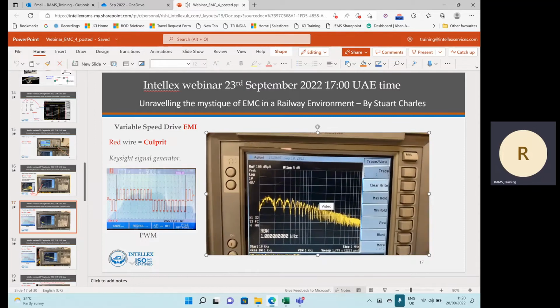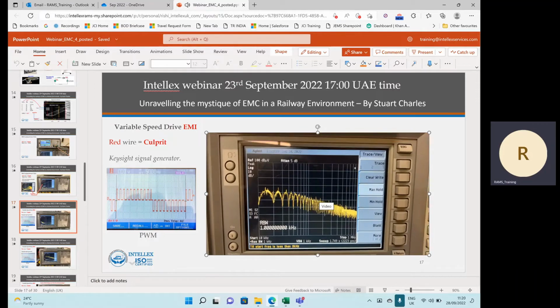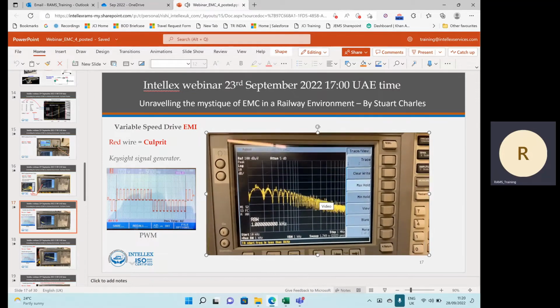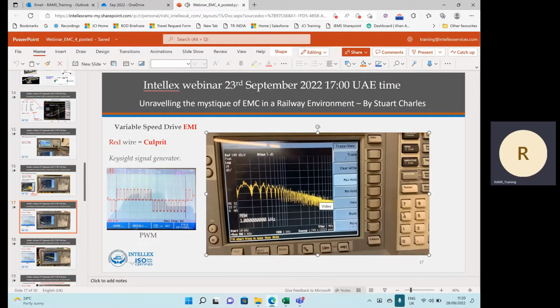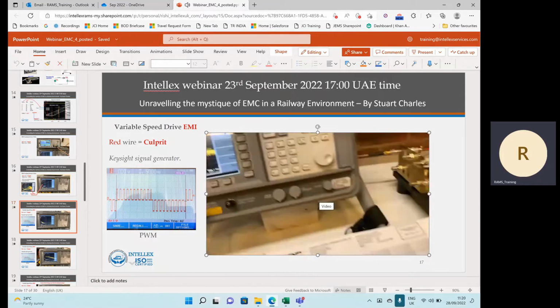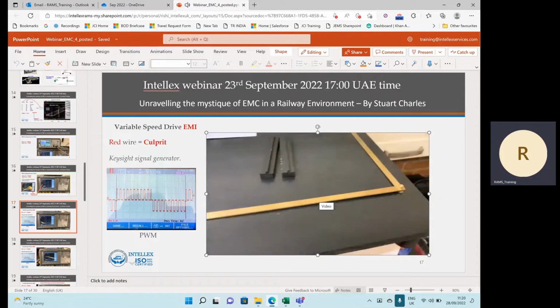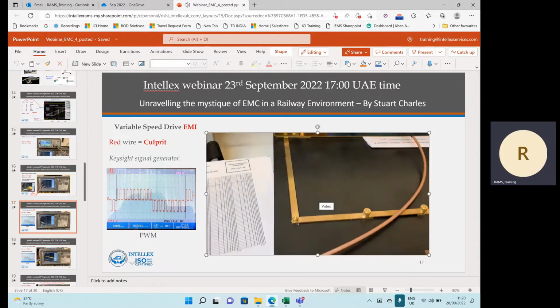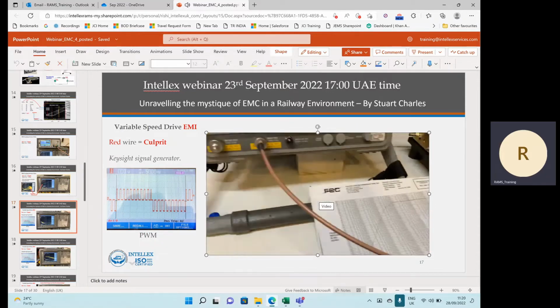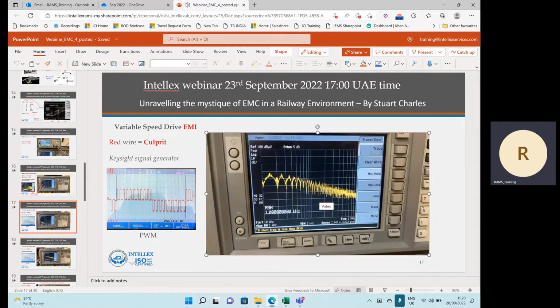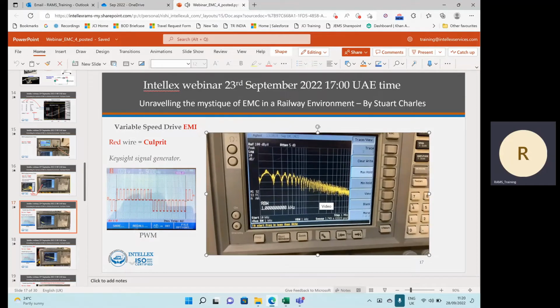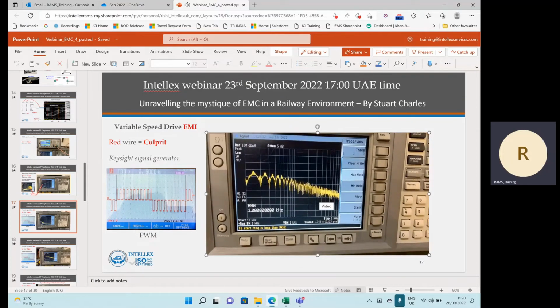We'll now max hold that, and what we're going to do is measure the contaminated current flowing through the external system earth, this earth here. Because if we do get current flowing through that earth, we've really lost control of our electromagnetic interference - or we could have, if we have a poor installation. So I'm just going to turn this video off for a second.